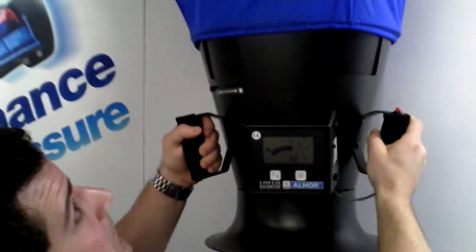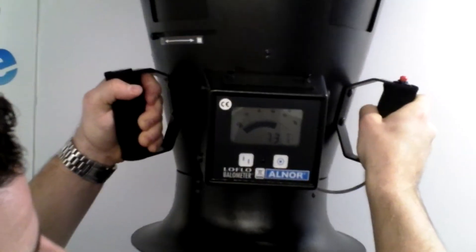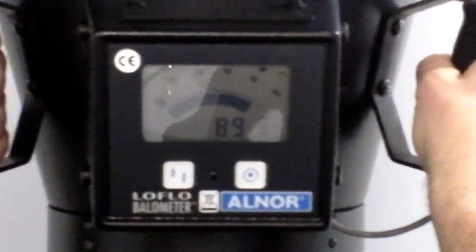As I plug the balometer up here, you will see that the CFMs are staying up at 80 CFM plus on the Panasonic fan. This is what we call SmartFlow technology.